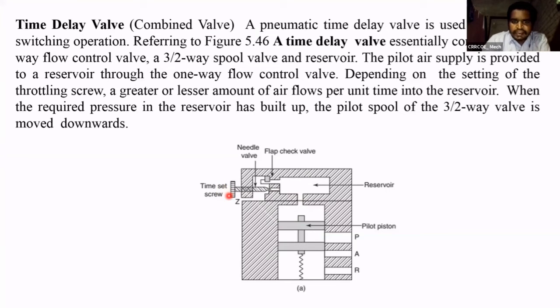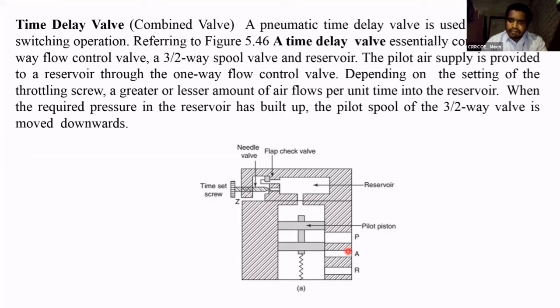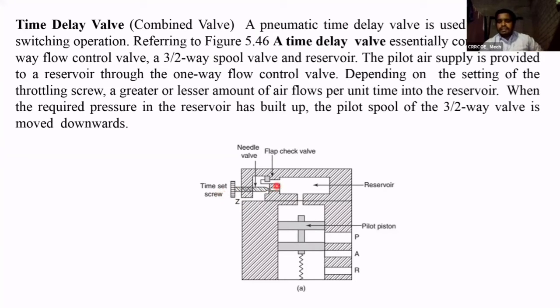The pilot air enters into the port. Continuously the air fills the chamber; the pressure of the air increases. At certain pressure it pushes the spool down against the spring, opening port P to A. If pressure increases more, ports A and R are connected. The movement of this spool depends on the pressure of the air in the chamber above the spool. The increase of pressure depends on this port/jet — we have a screw to set the opening. How much time it takes for pressure to increase enough to move the spool is decided by this time set screw.